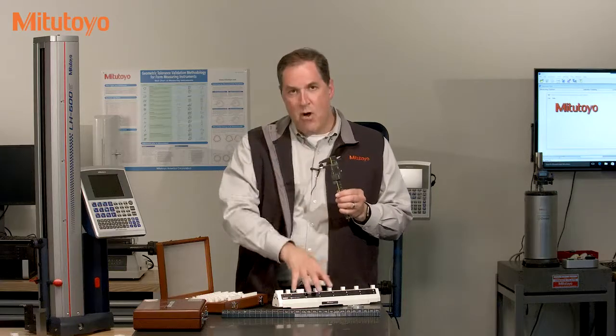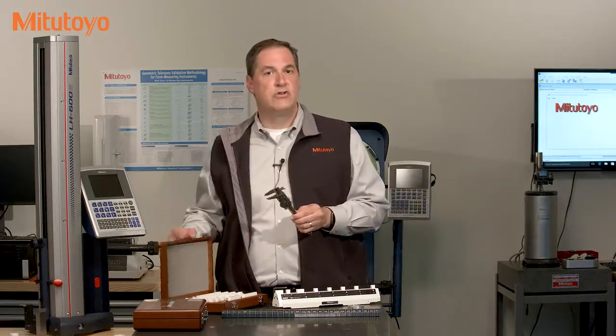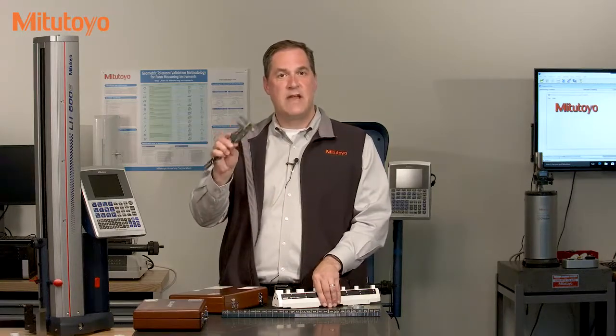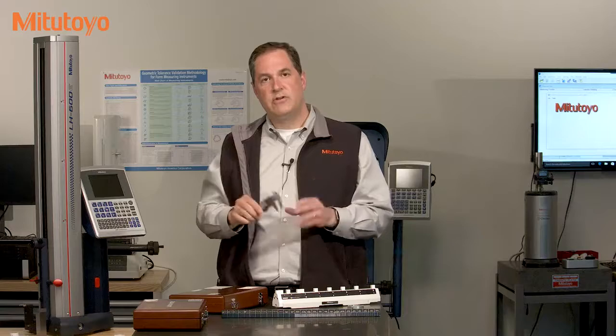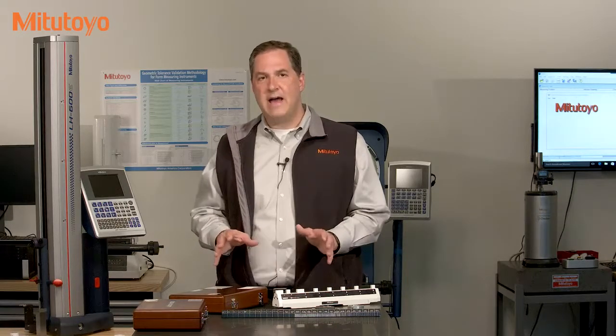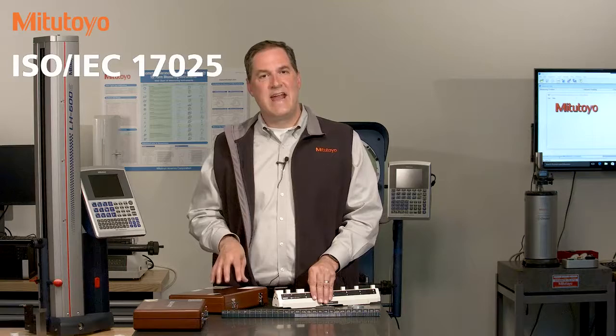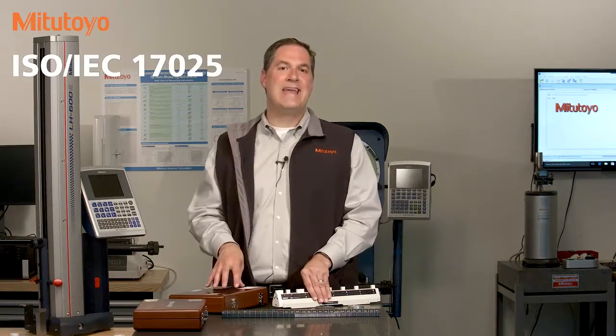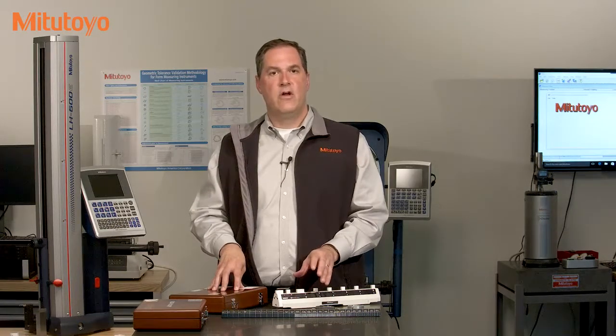But how does the owner of this caliper trust that system? They are relying on a chain of multiple calibration suppliers to ensure the quality of their measurements made with this caliper. The best way to ensure rock-solid traceability is to use what we call accredited calibration laboratories. The use of accredited calibration labs is required in many industries, but even if not, it is highly recommended. The standard used in accreditation is called ISO/IEC 17025, and it is an internationally recognized standard for competency in calibration and testing.